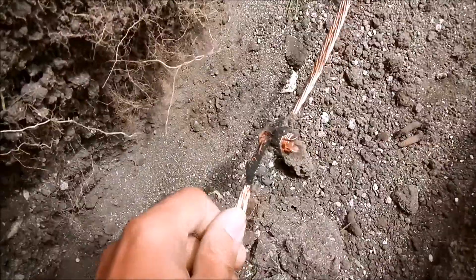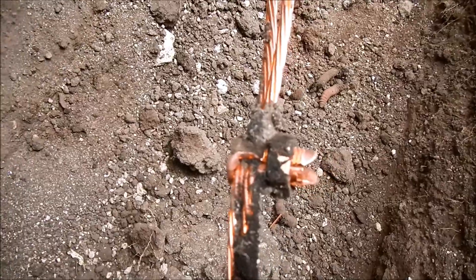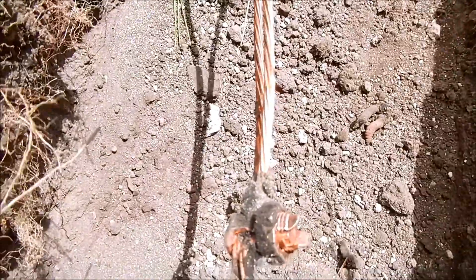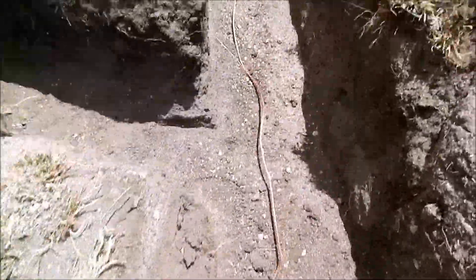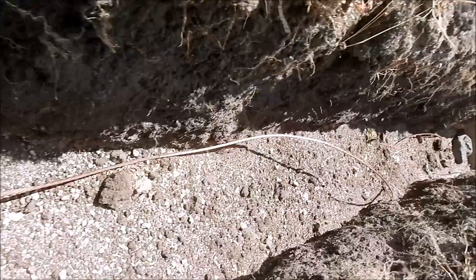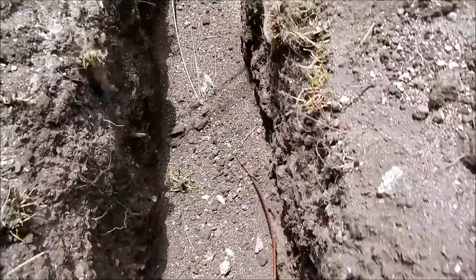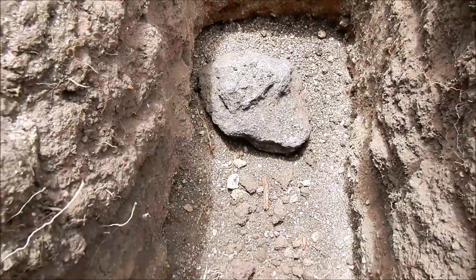We've also got our split bolts and noalox with electrical grease holding this together. We've got a split bolt for every radial line we run out away in our grounding system.